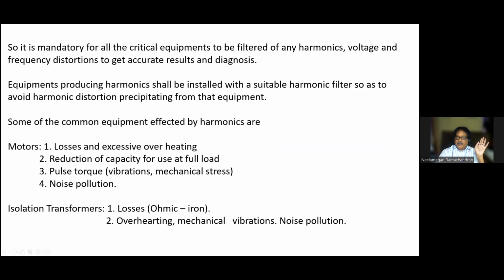So you have to be very careful about harmonics. In what equipment do harmonics play a role? In motors, there are losses, excessive overheating, and reduction of capacity for use at full load, because certain motors will trip without even reaching full load. We will be breaking our heads, wondering what the problem is. The operator will say the motor just tripped. So we put in a power analyzer, clamp tester, whatnot. We monitor carefully whether it is going to maximum load, whether it is tripping in that area. Nothing like that. It will be at 80%. It will not go over that. But the motor will trip. So this is the problem.